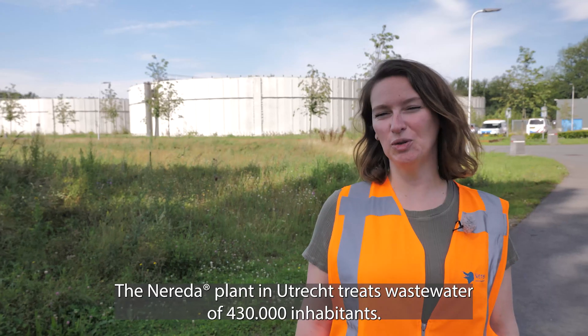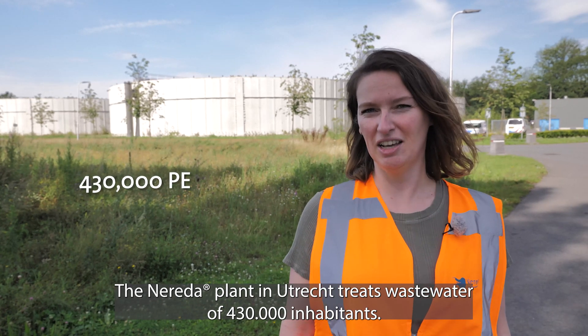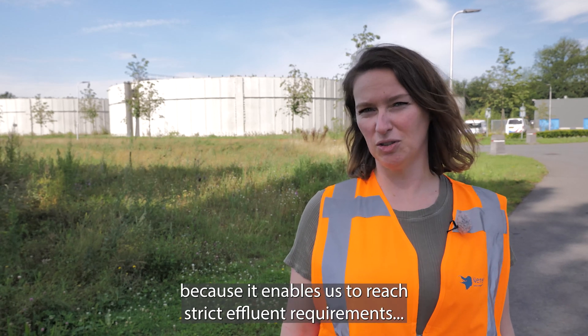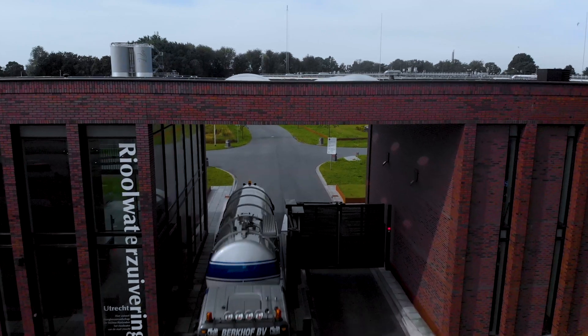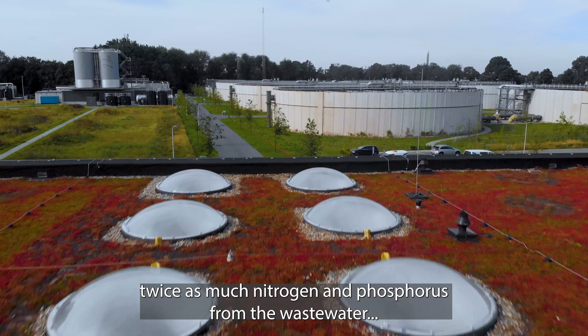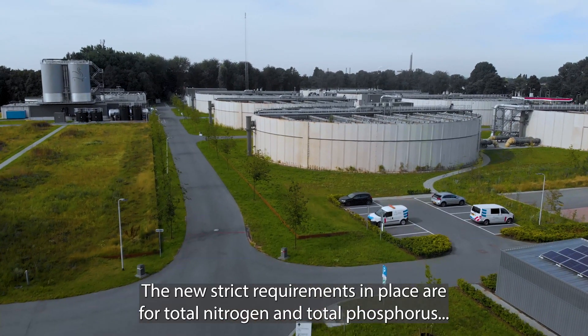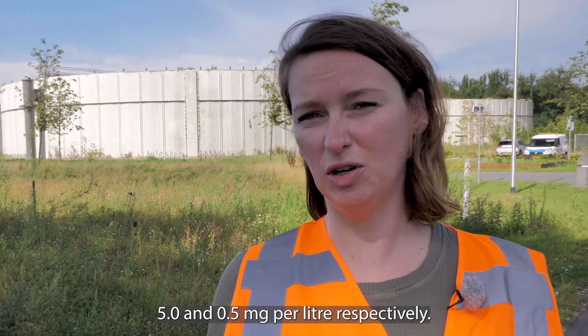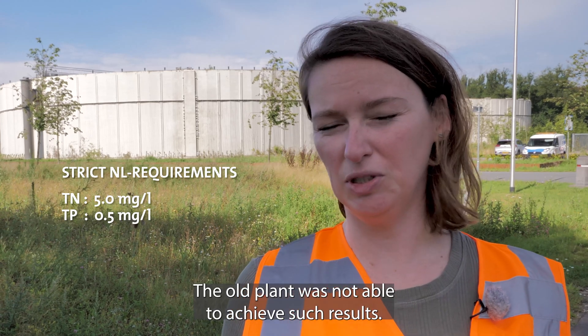The Nereda plant in Utrecht treats wastewater of 430,000 inhabitants. De Stichtse Rijnlanden selected the Nereda technology because it enables us to reach strict effluent requirements while operating in a compact plant. The new plant is able to remove twice as much nitrogen and phosphorus from the wastewater as the old plant could. The new strict requirements for total nitrogen and total phosphorus are 5 and 0.5 mg per litre respectively. The old plant was not able to achieve such results.